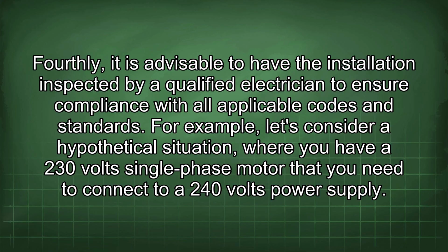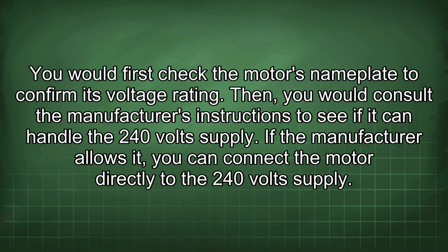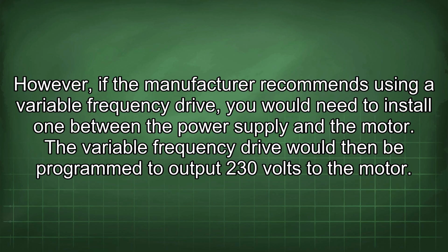applicable codes and standards. For example, let's consider a hypothetical situation where you have a 230 volt single-phase motor that you need to connect to a 240 volt power supply. You would first check the motor's nameplate to confirm its voltage rating. Then, you would consult the manufacturer's instructions to see if it can handle the 240 volt supply. If the manufacturer allows it, you can connect the motor directly to the 240 volt supply. However, if the manufacturer recommends using a variable frequency drive, you would need to install one between the power supply and the motor. The variable frequency drive would then be programmed to output 230 volts to the motor.